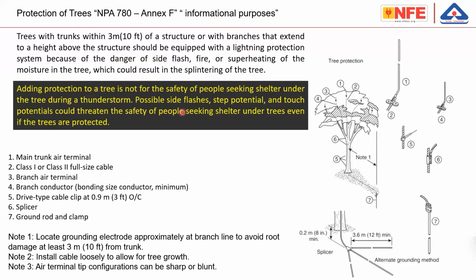The second para of the standard says, adding protection to the tree is not for the safety of people seeking shelter under the tree during a thunderstorm. Possible side flashes, step potential, and touch potential could threaten the safety of people seeking shelter under the tree, even if the trees are protected. So please don't try to apply this principle to protect people.